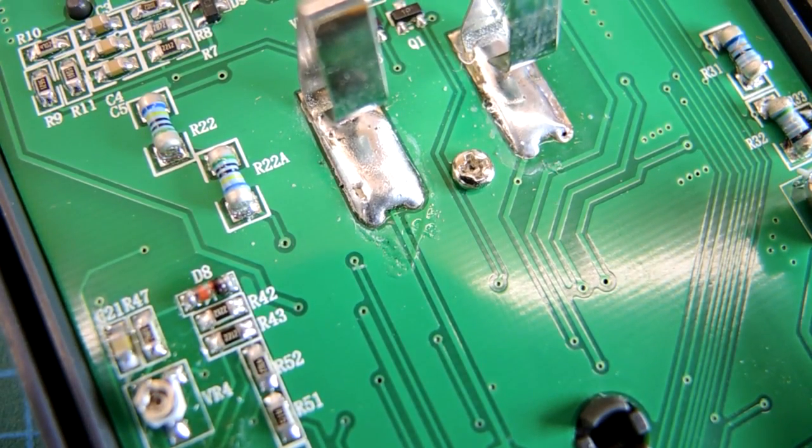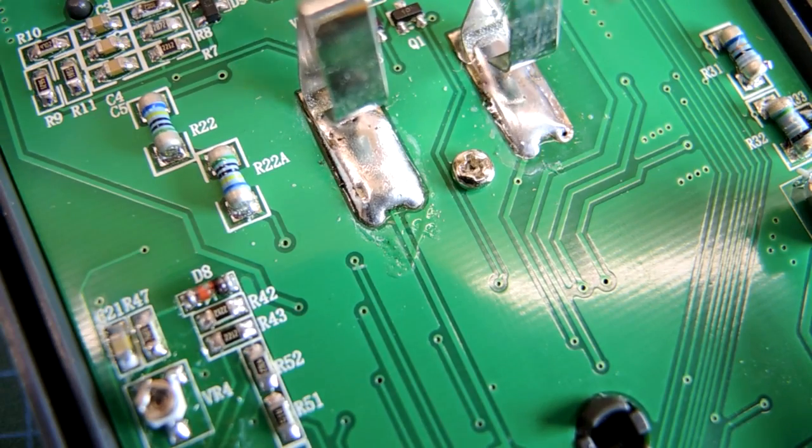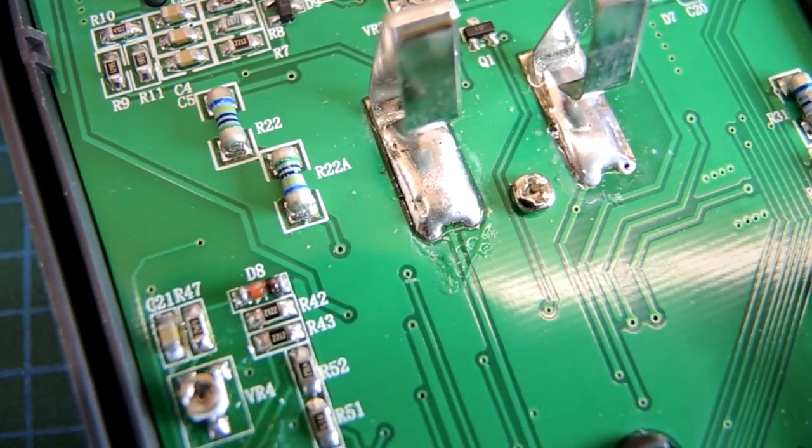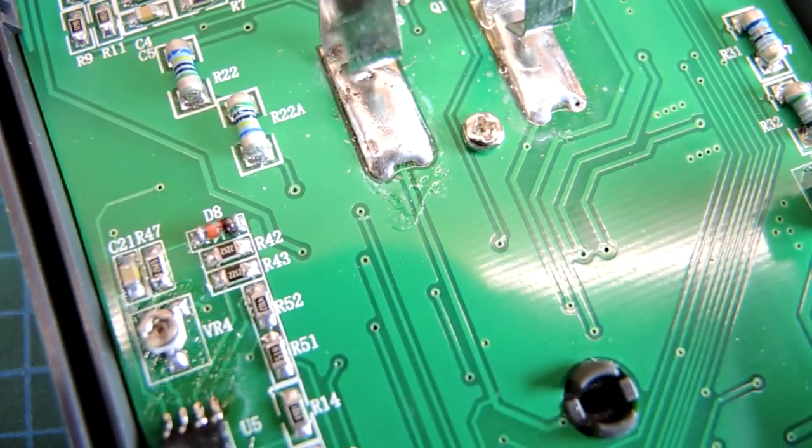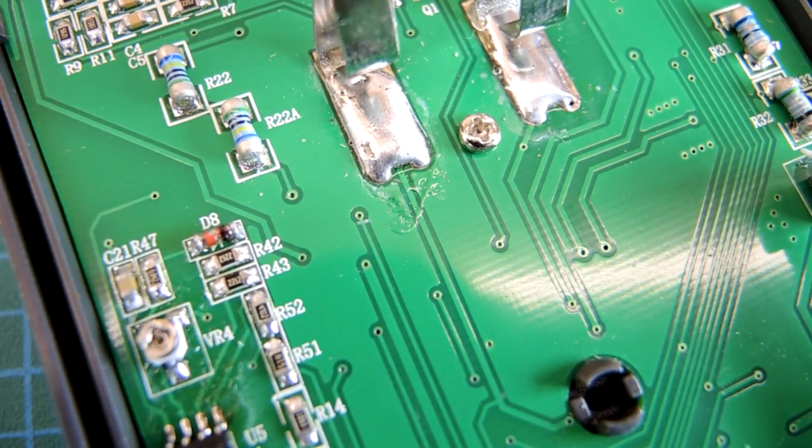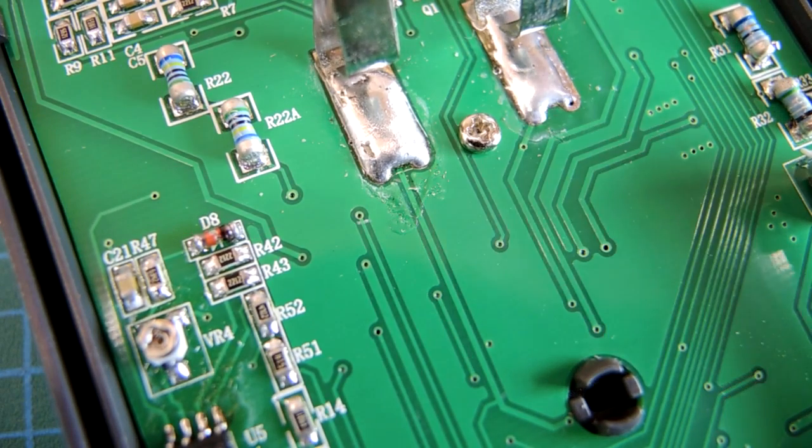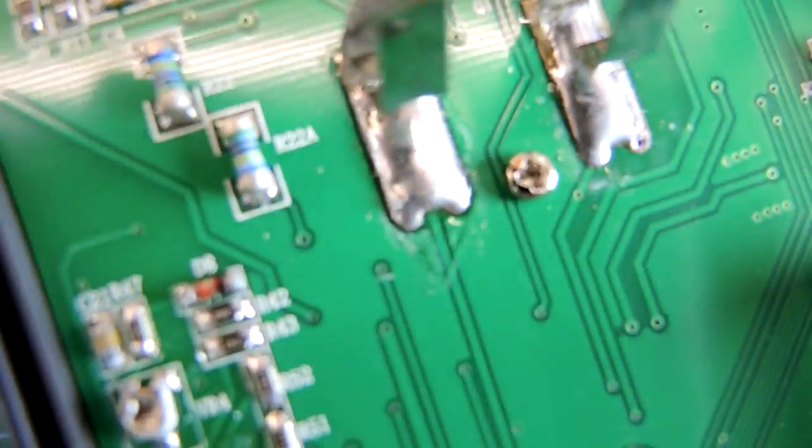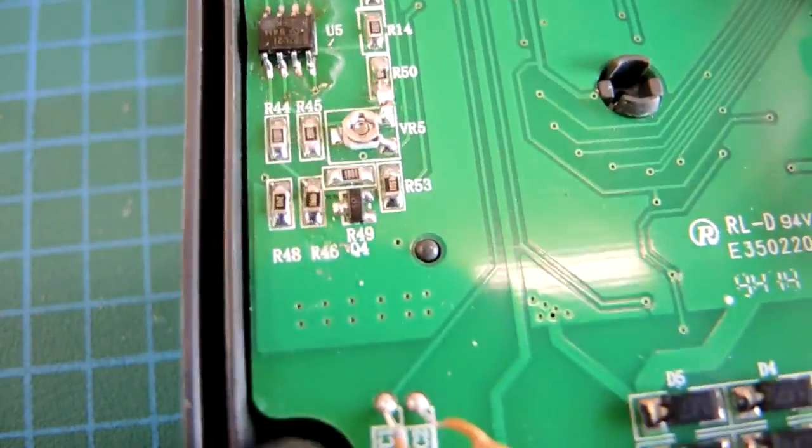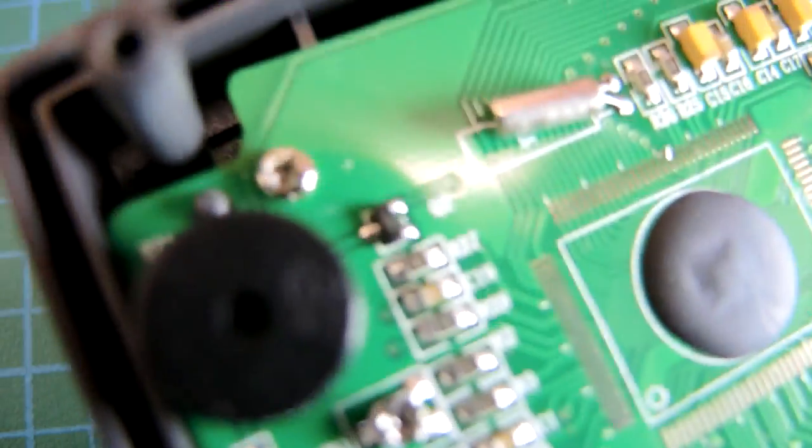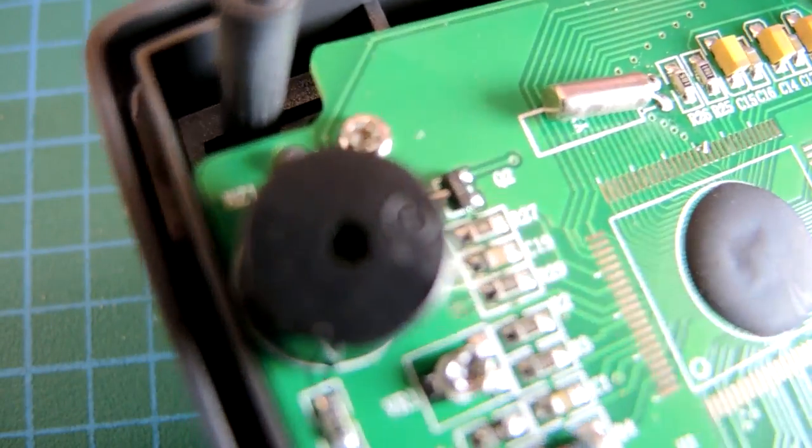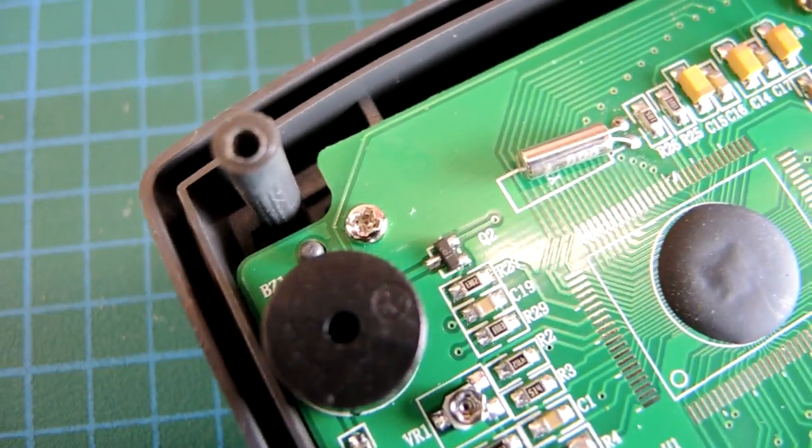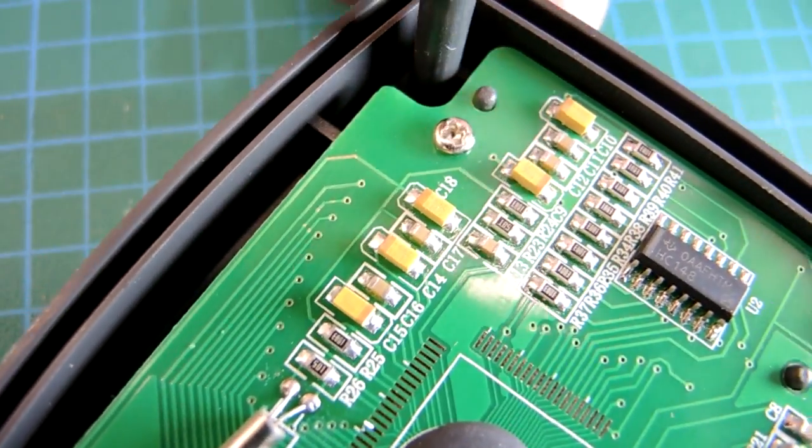Just another note on workmanship. I was just assembling the meter back together. You can see the screw head, and it seems to be coming over onto other trace, and that's not an optical illusion. Essentially, the head is so large that if I was to really torque down this screw and cut into the resist, it would actually short the trace out to the plane. Clearly something that you would not want in a meter. That's what often befouls smaller vendors. They can't get the electromechanicals right. And that's always a challenge.